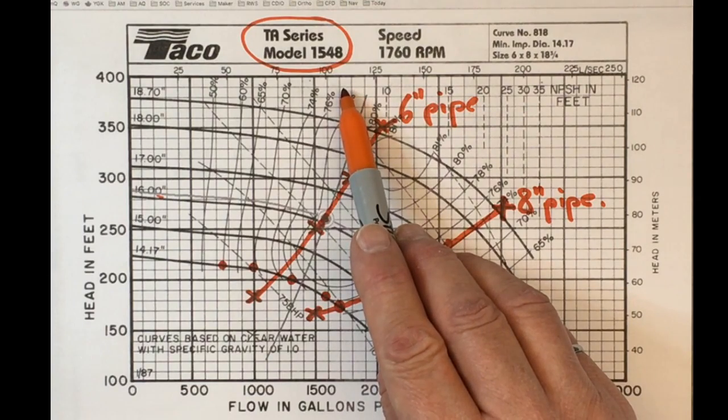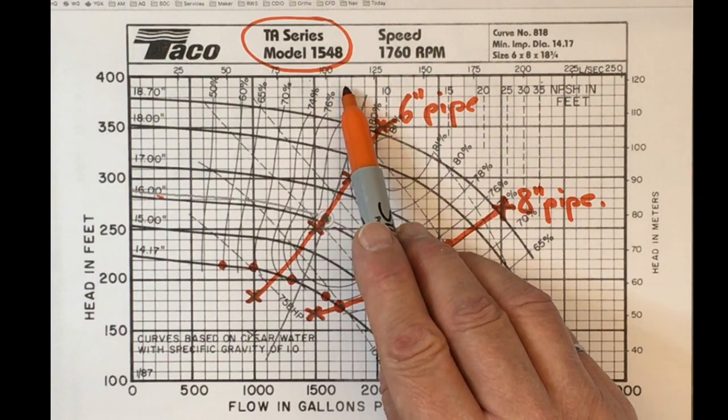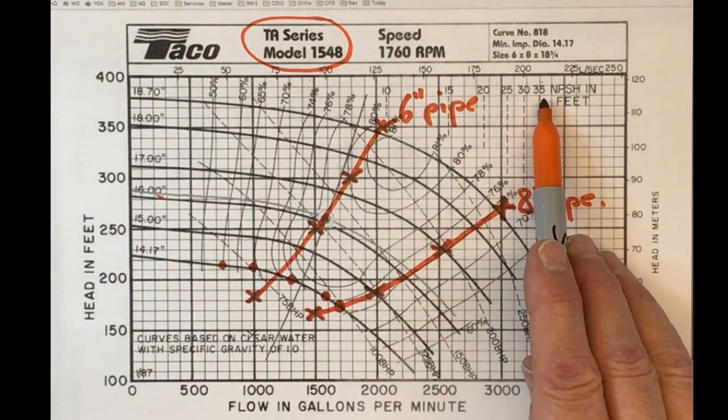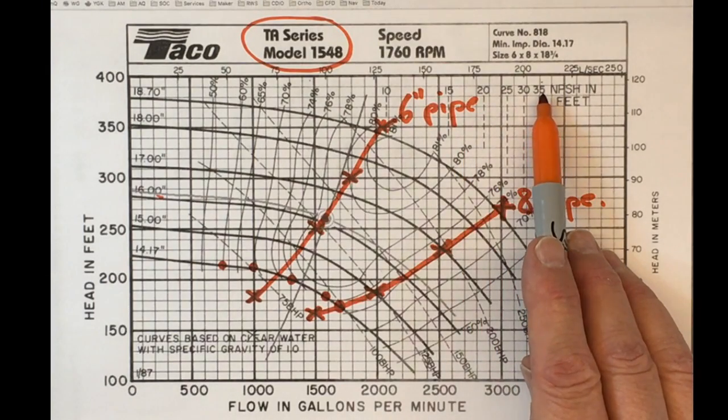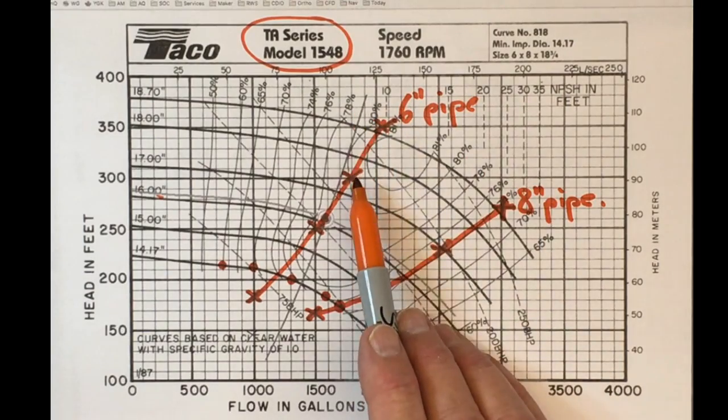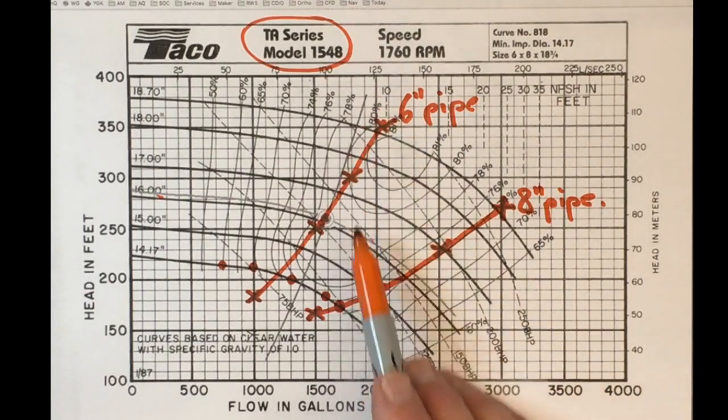So let's hang on to that and we'll check up on that later and find out if we're okay. If we went up to higher pump speeds, we'd be going to a much higher NPSH and we might have to do something to avoid cavitation. But we'll check this with our NPSH requirement of 9.